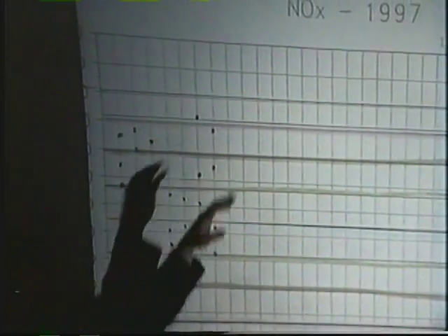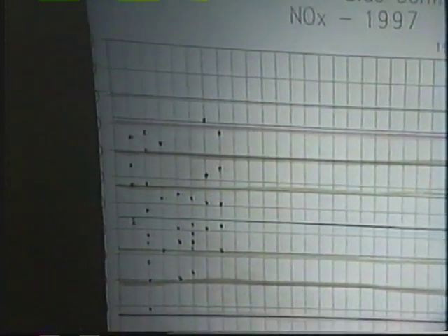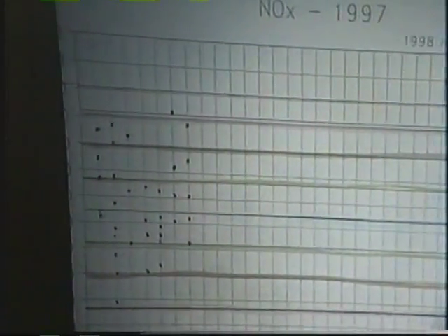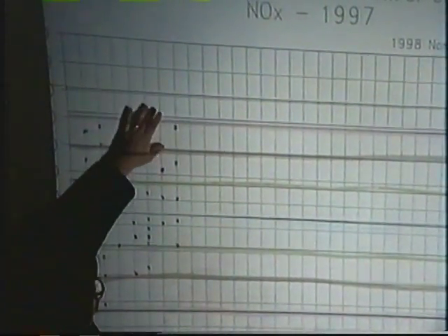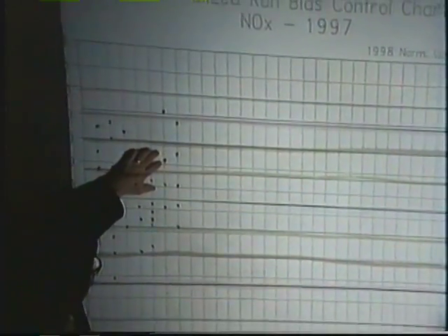Now in this case, and I noticed this when I copied this, here's an out of control point. The normal process would be, when that point got plotted, all the data from that run was rejected because this external check was telling us our accuracy is out of control. So the accuracy of everything else in that analytical run was out of control. This run would have had to be repeated based on that point.